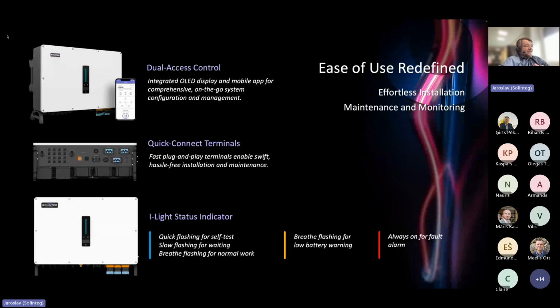We have also a I-Light status indicator. These are the flashing lights which you see. When it's quick flashing, it means the inverter is in self-test. When it's slow flashing, the inverter is waiting, and when it's breathe flashing, the inverter works normally. When this color changes to yellow, that means there is a battery warning, a low battery warning. When it's always red, it means the inverter has some problem, it's in a fault alarm.